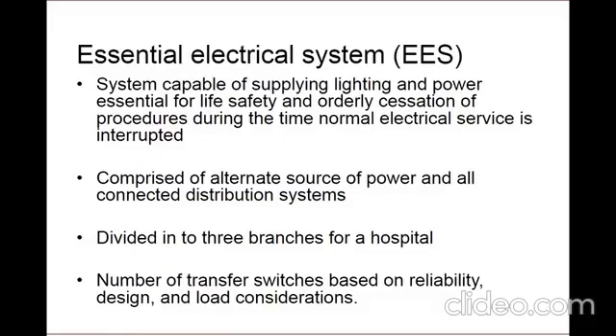The EES as a whole is defined as a system capable of supplying lighting and power essential for life safety and orderly cessation of procedures during the time normal electrical service is interrupted. The EES is comprised of the alternate source, which is typically the generator, and all of the connected distribution systems, including automatic transfer switches, distribution and branch panel boards, as well as their associated feeders. NFPA divides the EES into 3 branches: the life safety, critical, and equipment.